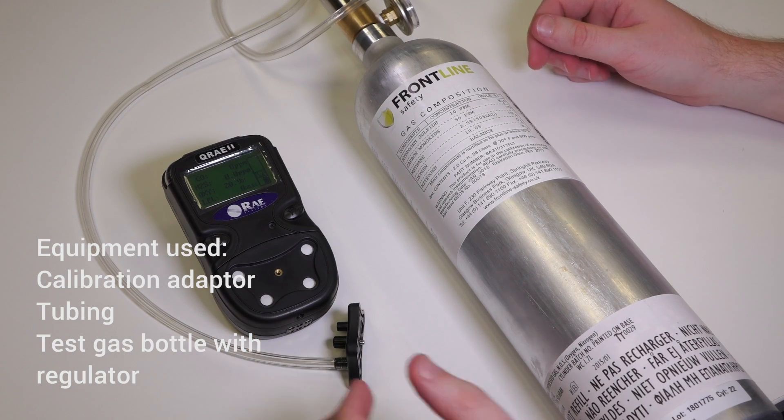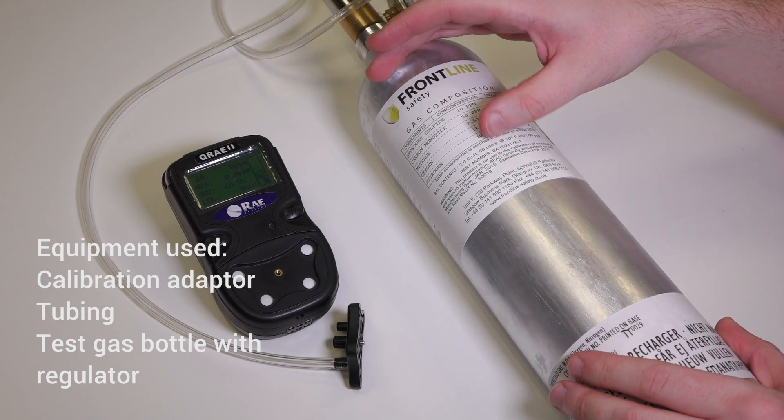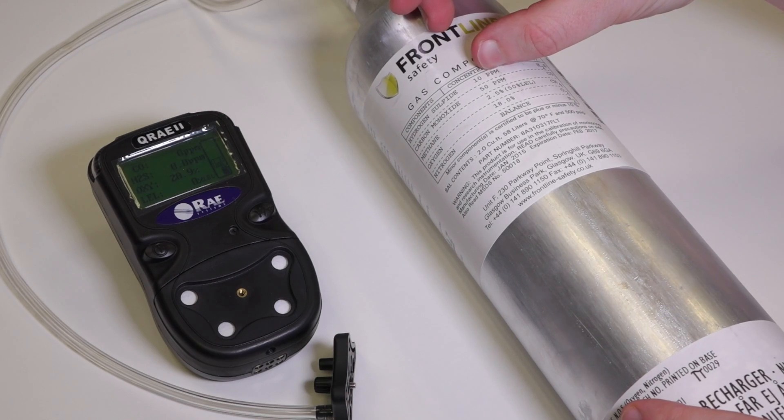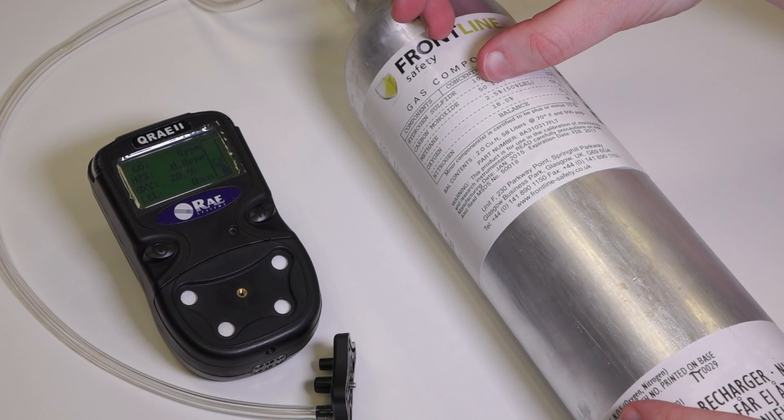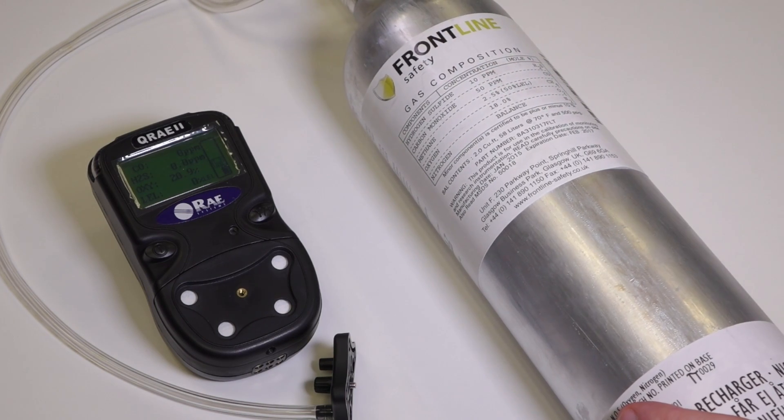To calibrate the QRAE II, you're going to need the calibration gas with the correct concentration for the unit. In this case it's 10 ppm H2S, 50 ppm CO, 2.5% methane, and 18% oxygen.